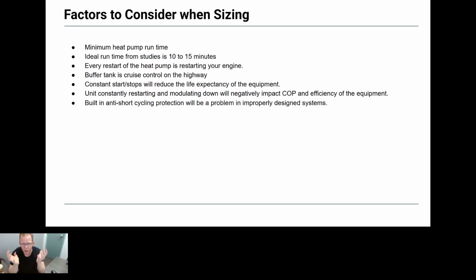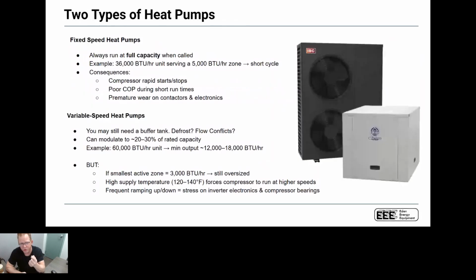Now, when we look at the buffer tank and the factors we need to consider when sizing it, I touched on some of them. One is the minimum heat pump run time. There are a lot of studies out there that show the heat pump should run 10 to 15 minutes. The easy example is just imagine if every single time you were going 20 feet in your car, you were turning your engine on and off. Not very good for it. So think of the buffer tank as the cruise control for your system. It limits those starts and stops to keep the system very, very efficient, maximizing the COP. And more importantly, it is your built-in anti-short cycling device.